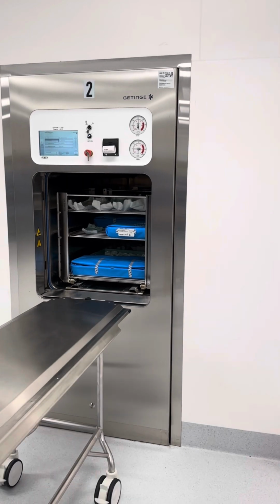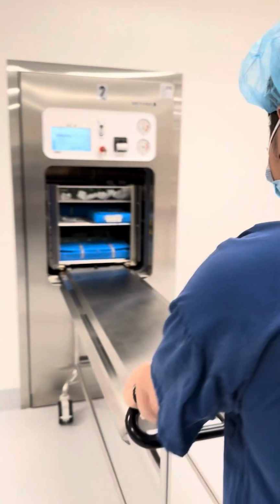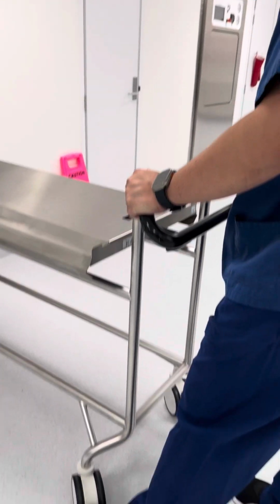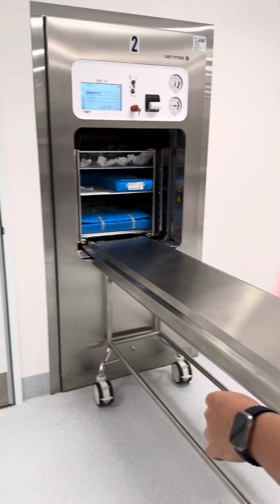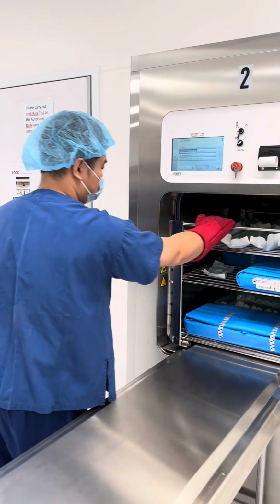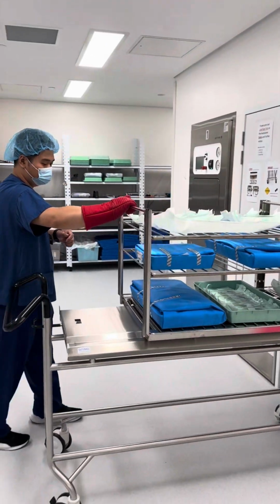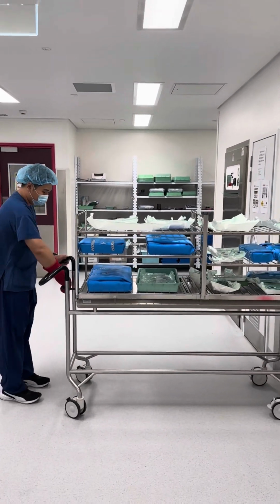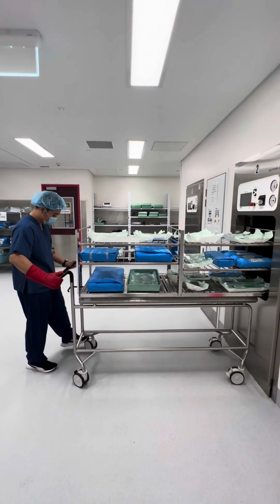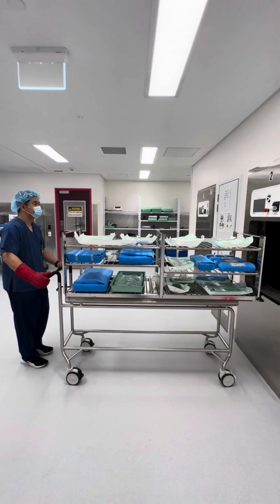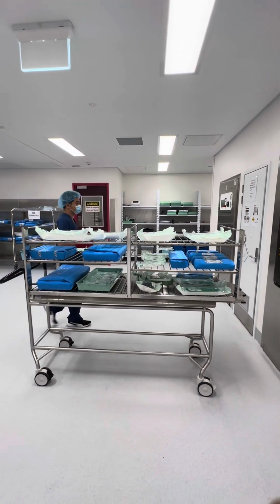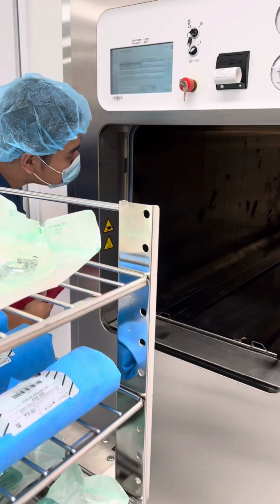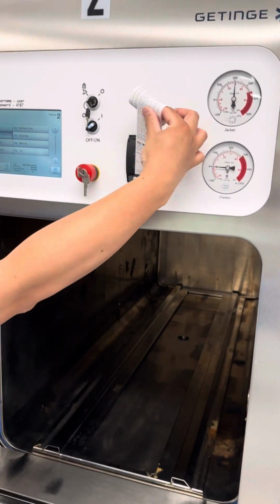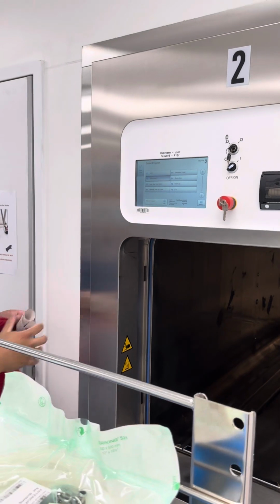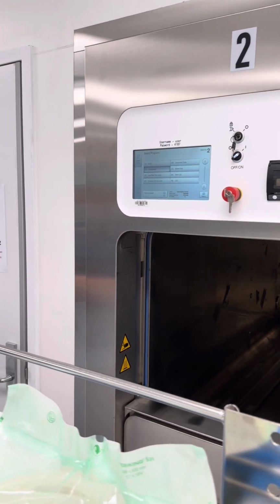When we unload the instrument from the autoclave machines, we must secure the trolley before unloading the cart. The cart will be very hot. We must wear the mittens to protect our hands when we pull the cart out. After you finished unloading the cart, quickly check inside the chamber for any items that might have dropped. Then we can proceed to close the door and push the trolley to the designated area for cooling down the equipment.